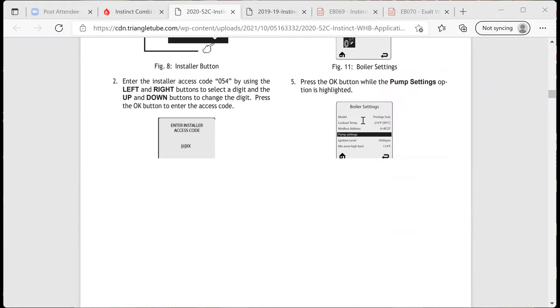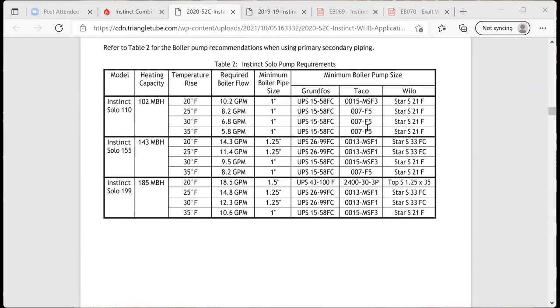You can see we have 007s in here, but just notice they're not ECMs. These are just standard pumps. And the 0015 shows the standard pump. We thought that the Taco on the third speed had that safety feature where it shut off, but it doesn't. So you can use an ECM to gain that 20 degree delta T. And then 0013 and 2699.